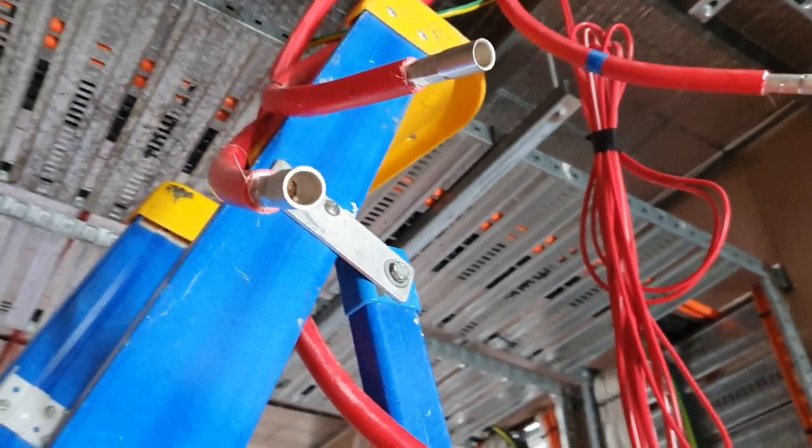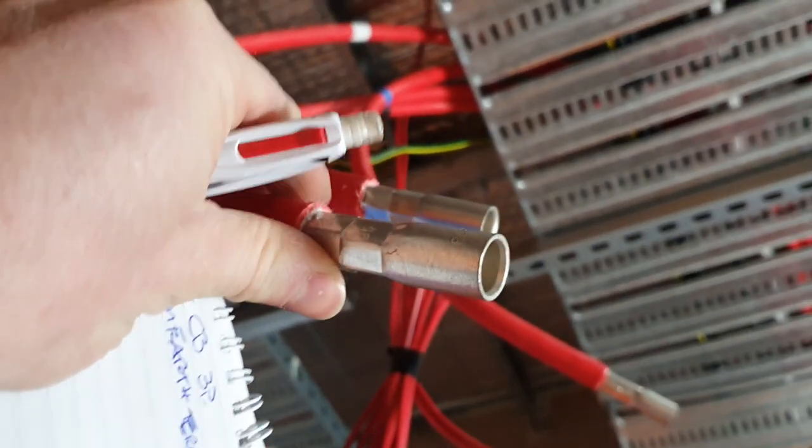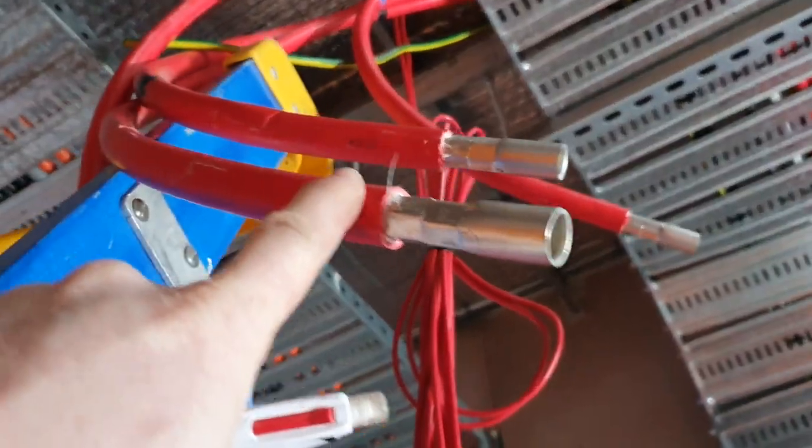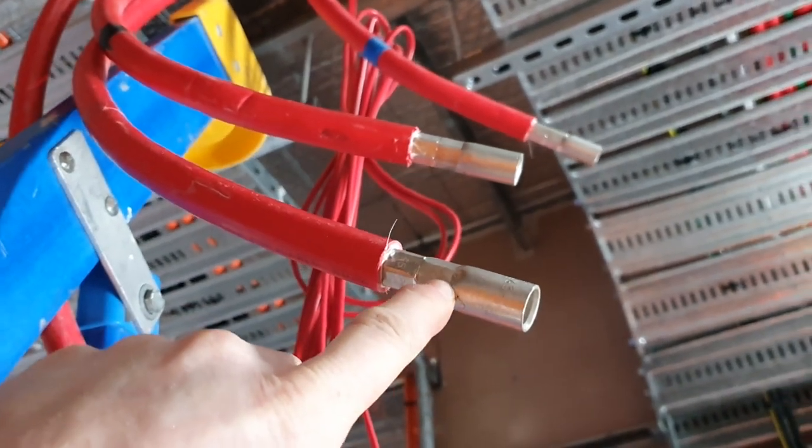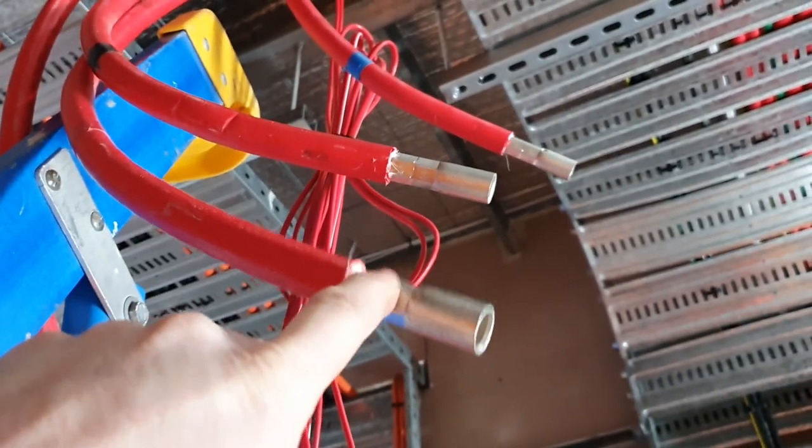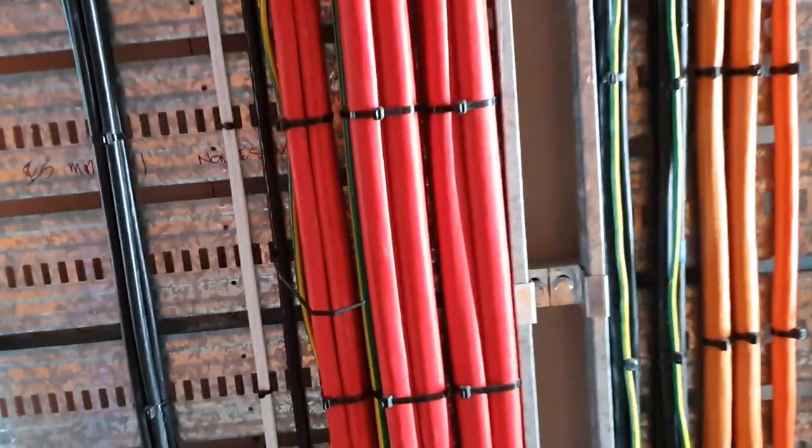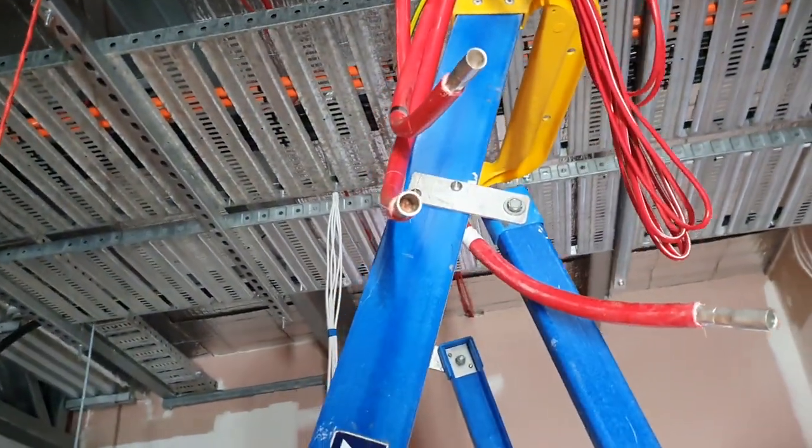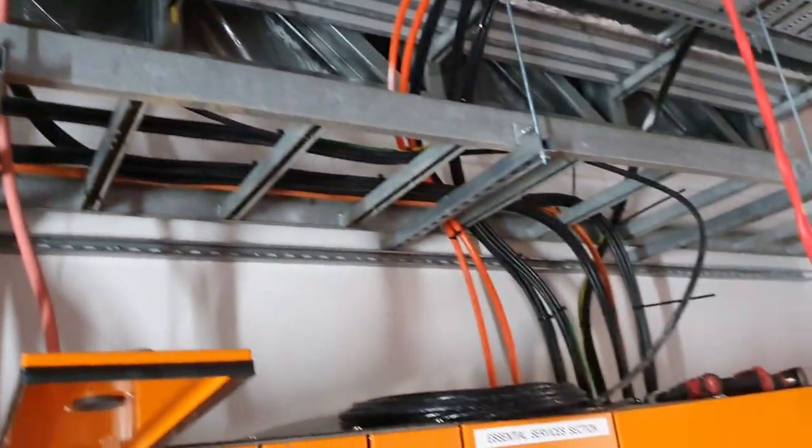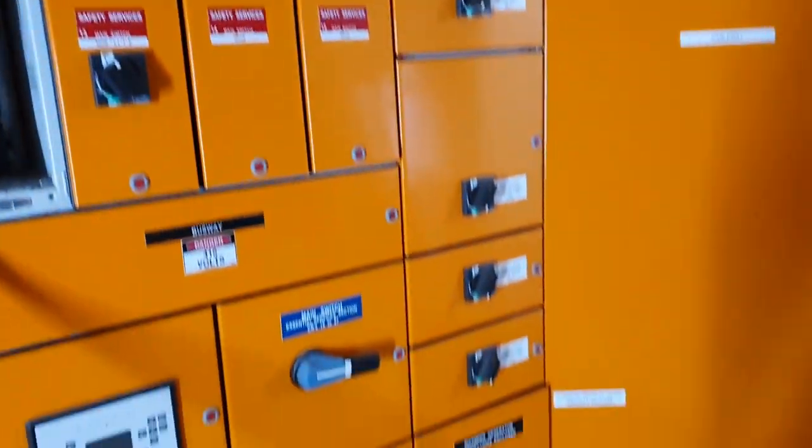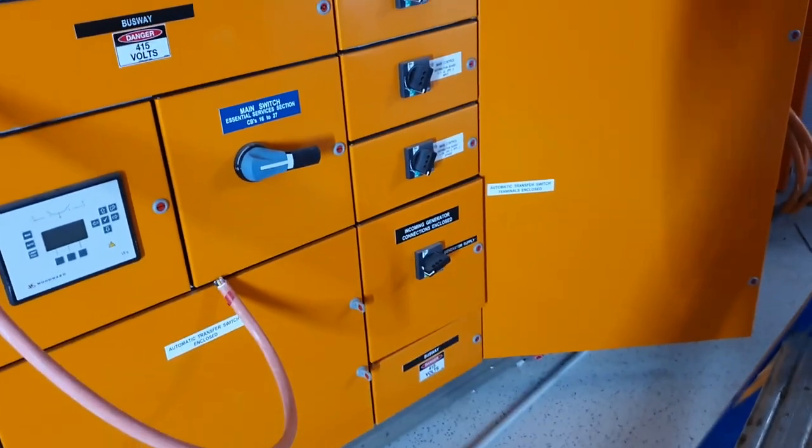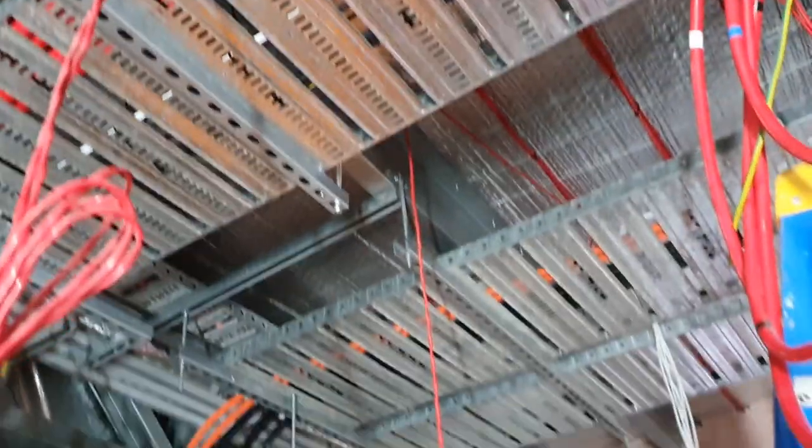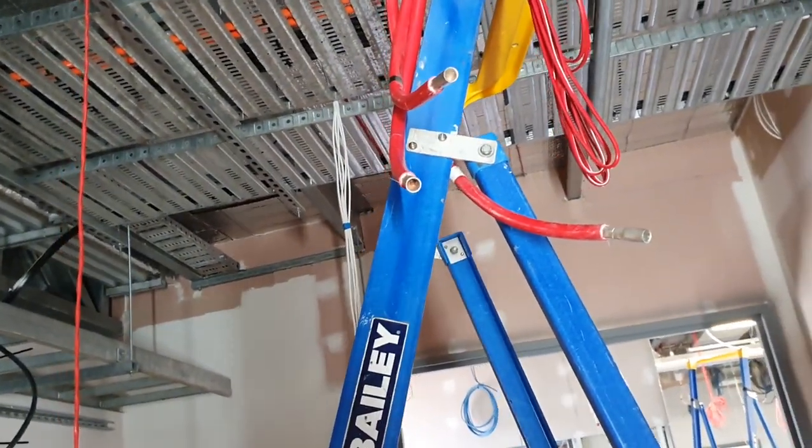I can video over to my fuck up here, boys. We're going to have to extend these. We've got a bit more cable there to do it. I'm not sure whether I gave the measurement wrong or it got translated wrong. But they should have been the same length as the consumer mains and they were the perfect length. So I'm not exactly sure how that happened. But they've got to go down the tray across there and down into that way there. So that'll get fixed up. Heat shrink the joint, it'll be up on the tray there. It won't be too bad.